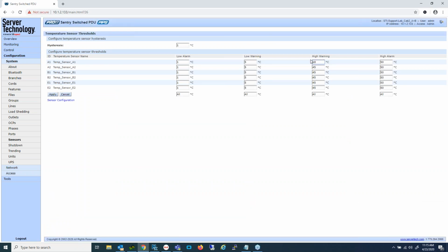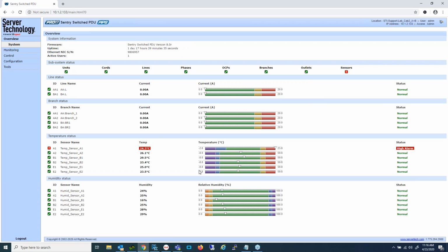I'm going to lower these values to be less than the current value, which will result in—let's take a quick look—a high alarm condition. So we see that the system is recognizing that we have a high alarm.